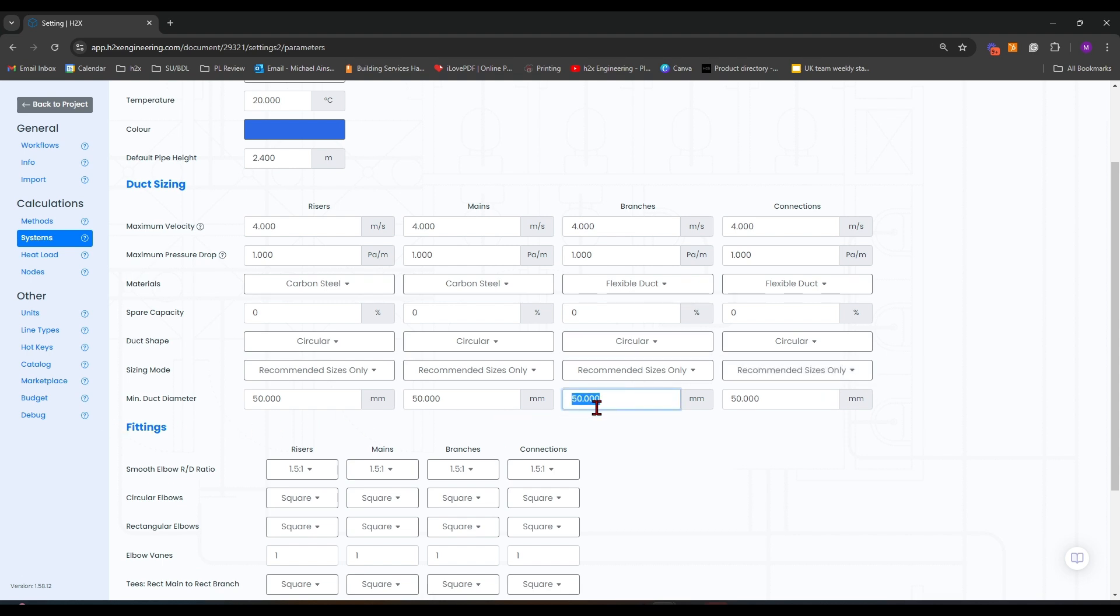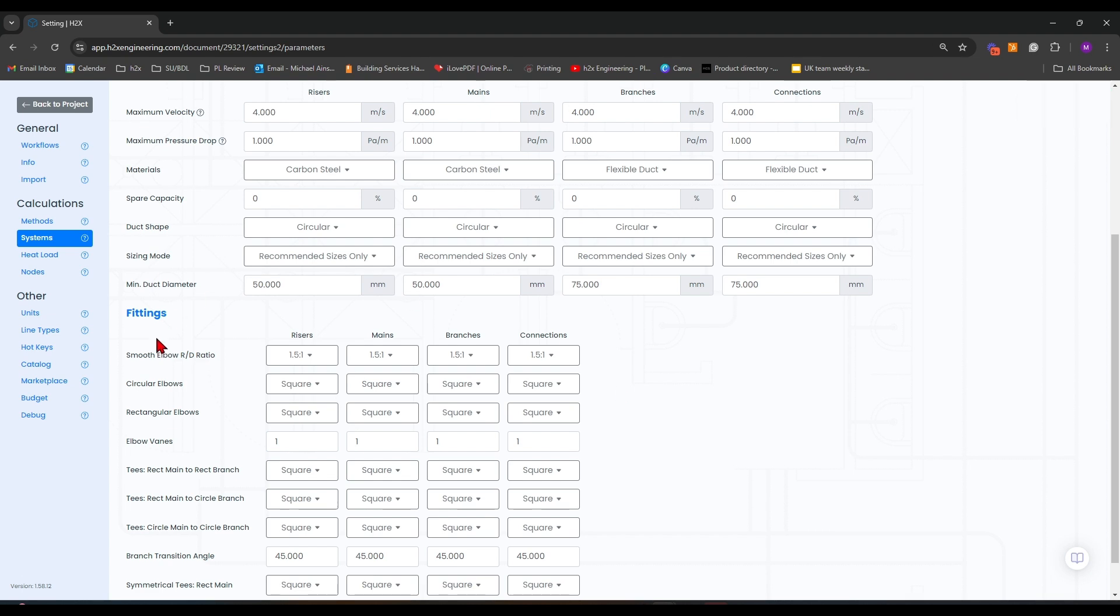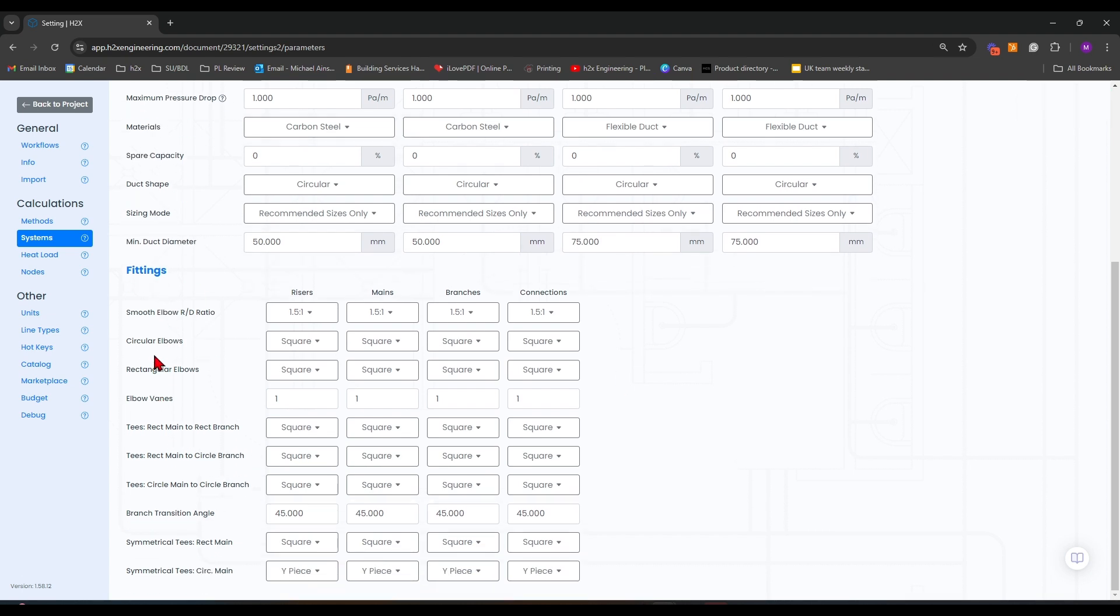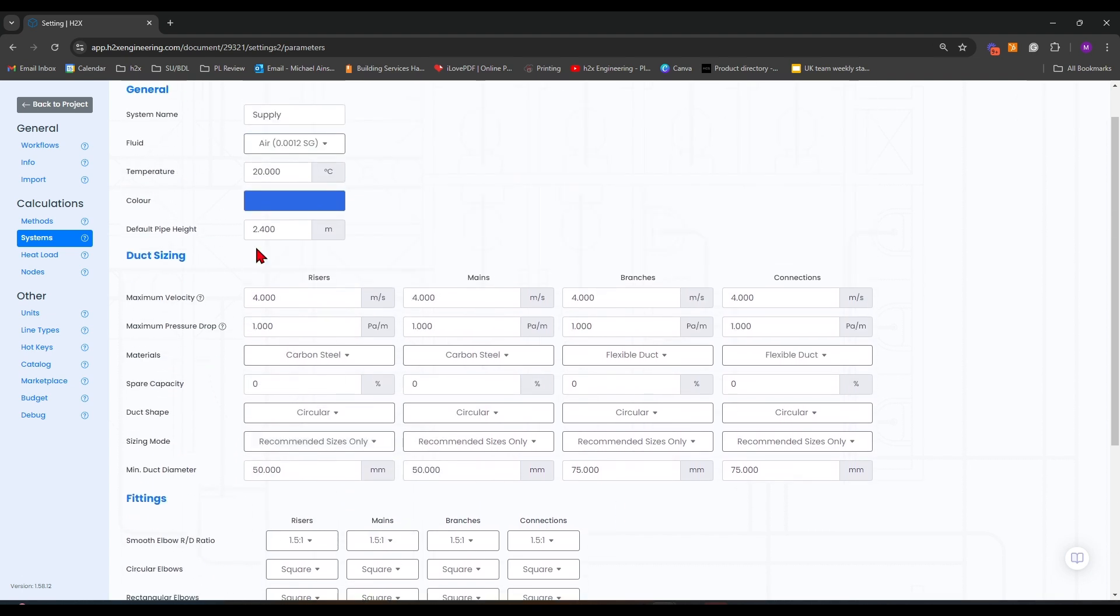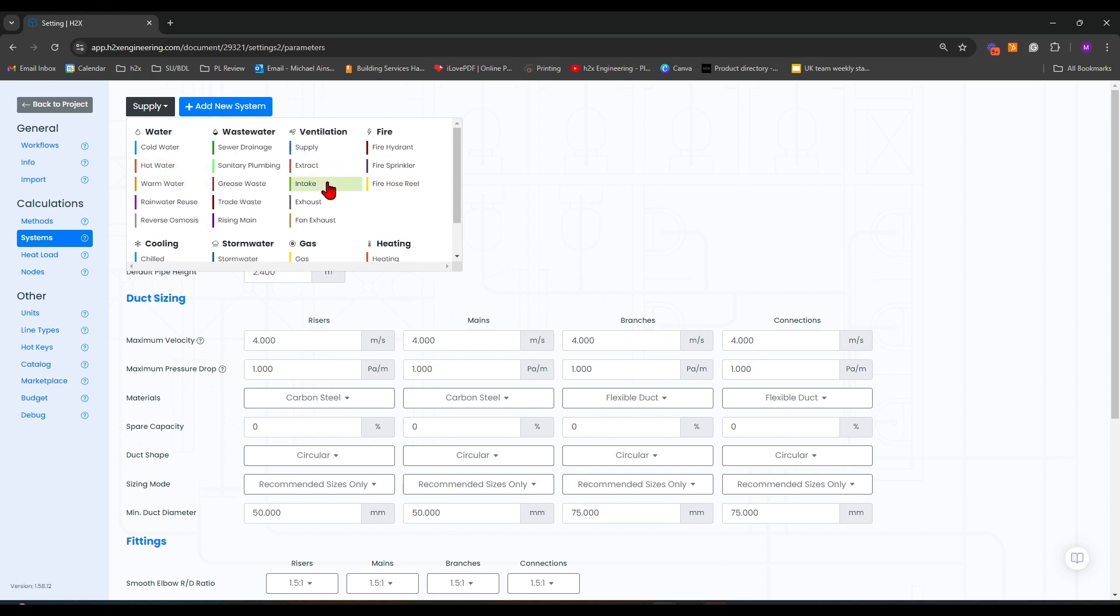For my branches and connections, because I'm using flexible duct, I'm going to set these as 75mm minimum size as I know this is a common practice in the UK. You can also add information for your fittings down in the menu here.